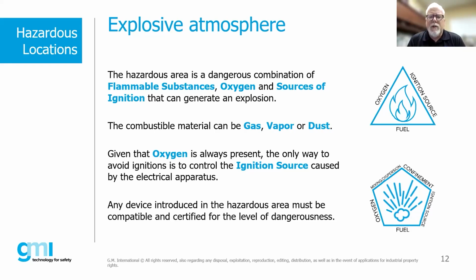The sources of ignition will really come in the form of either heat, that could be from something generating a tremendous amount of heat, or it could be from an electrical arc or spark. So when we think about intrinsic safety, that's where we're really focusing our attention, trying to minimize that ignition source to below the minimum ignition level of whatever potential flammable mixture is in the environment.